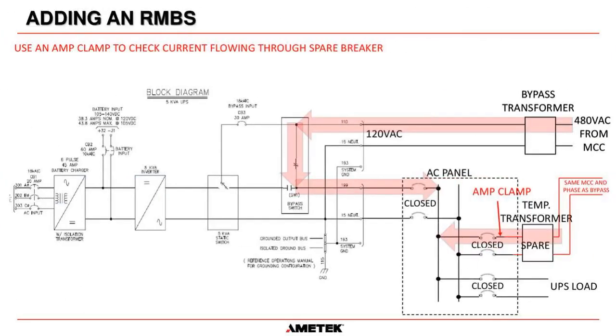The next thing we need to do is make sure, using an amp clamp on this cable here, that we are actually supplying current through that breaker. That proves that this temporary transformer has taken some of the load, which means this breaker has closed correctly. It lets us know that we can open this breaker here without any issues, because we have seen current flowing through here. We're just double checking, triple checking everything to make sure our critical loads are maintained.